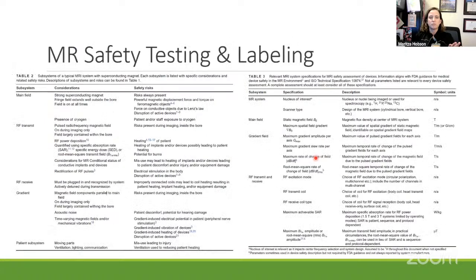Again, these are 2 small tables, but these are 2 tables from Task Group 334. Table 2 on the left is taking those subsystems of a typical MRI system discussed on the previous slide and showing their specific considerations and safety risks. And then Table 3 goes back to the relevant MRI system specifications for MR safety assessment of devices. So it's just knowing these specific values for your MRI system that is important. Then when a device or accessory has been given the MR conditional labeling and you have the product sheet with those labeling conditions, you can tell if it matches your system's specifications.